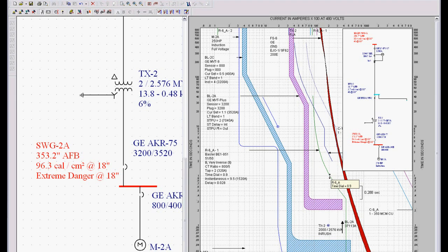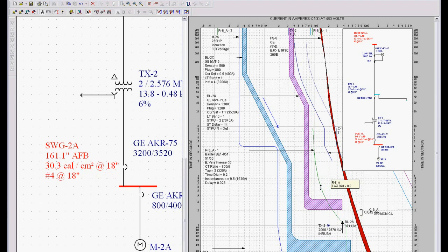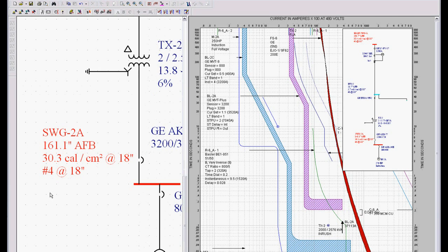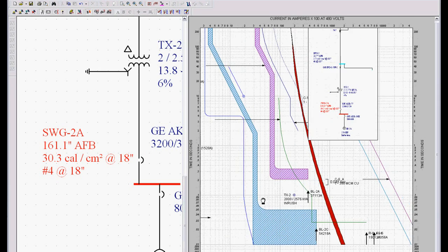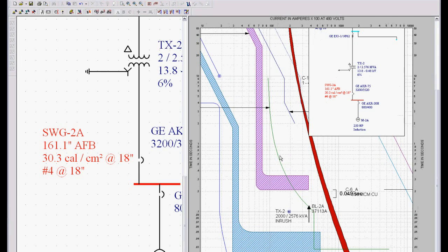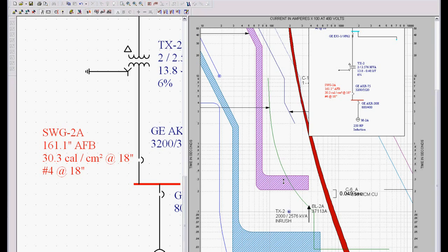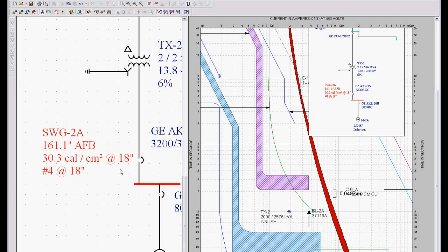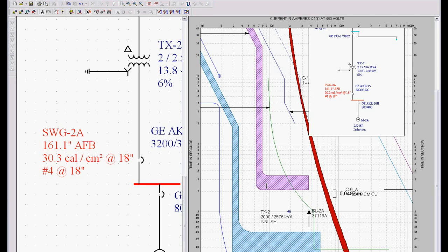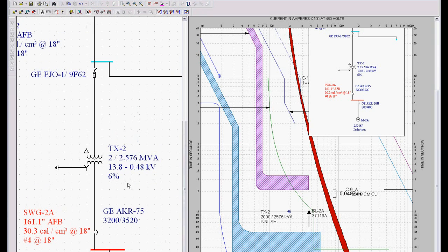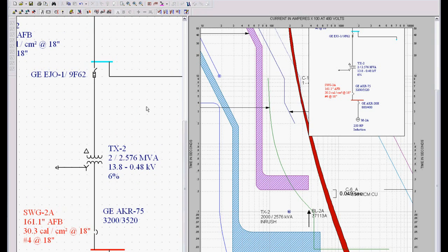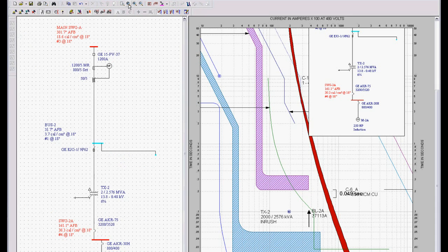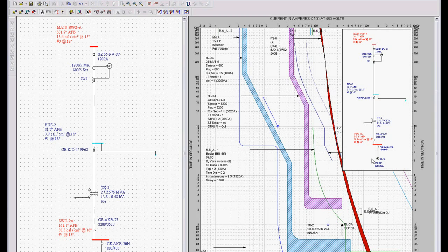Notice this is dynamic. As these curves change, so does my ArcFlash hazard. Notice what it does is in order to get a number 4 PPE, I have to have a very, very low setting. Well, what that's going to do now is that allows my 480 volt fault on this bus to trip the upstream relay before the secondary main. Not a good thing because now I shut down multiple transformers that are daisy chained in the system. So what's cool about this is it is completely dynamic.